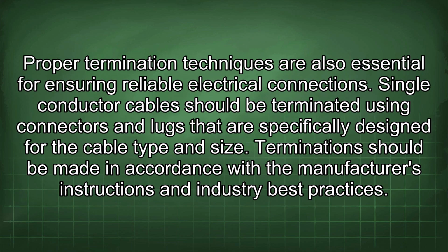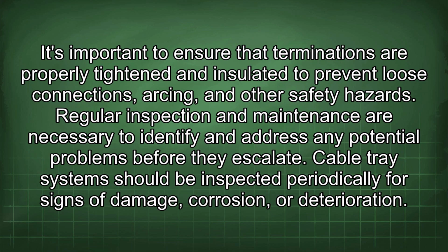Proper termination techniques are also essential for ensuring reliable electrical connections. Single conductor cables should be terminated using connectors and lugs that are specifically designed for the cable type and size. Termination should be made in accordance with the manufacturer's instructions and industry best practices. It's important to ensure that terminations are properly tightened and insulated to prevent loose connections, arcing, and other safety hazards.